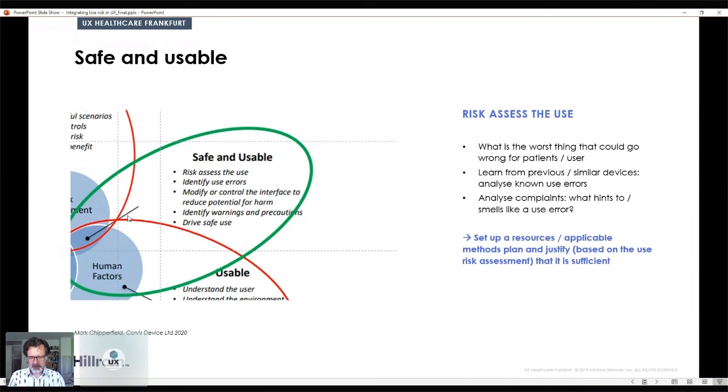And it's also a good point in time to get your risk manager on board. Risk managers, the guys I know, usually think about the electrical things that can go wrong, gravity things that can go wrong, biohazards, whatever. And I really recommend sitting down with this team and defining what your use is, what your use scenarios are, and seeing what can go wrong from a user perspective. So that doing something wrong is its own risk category further on in the process.